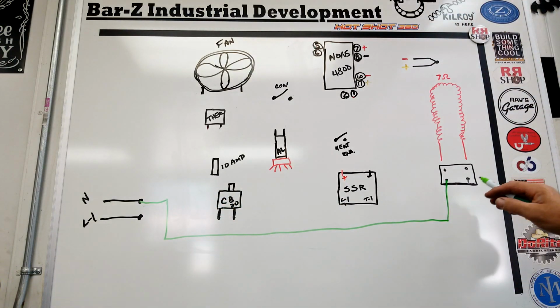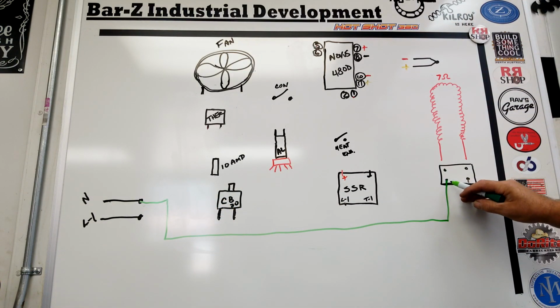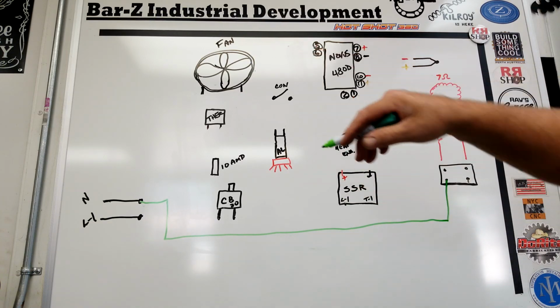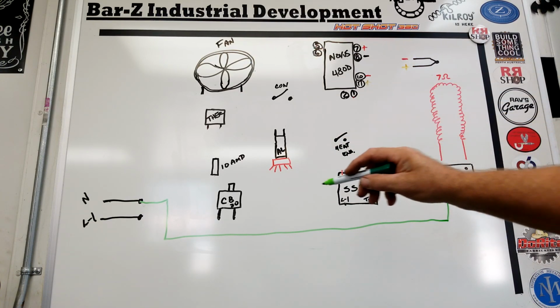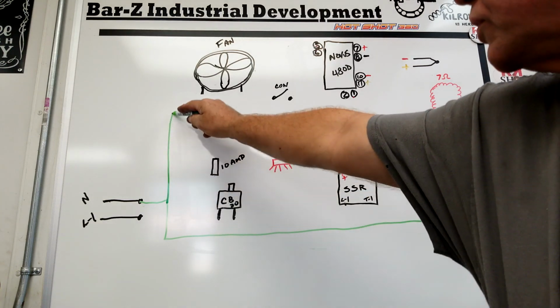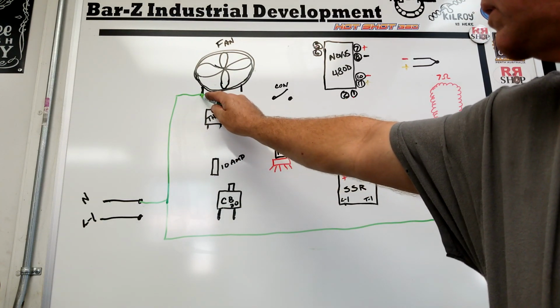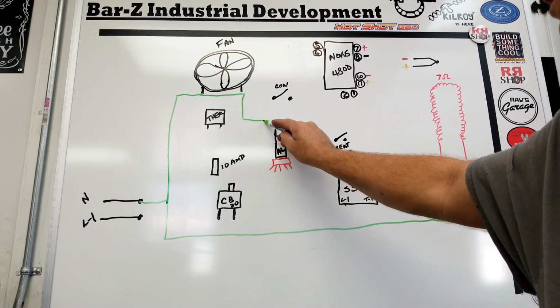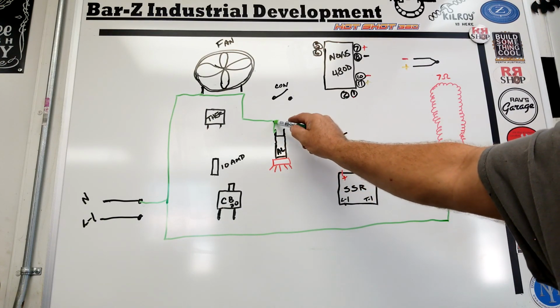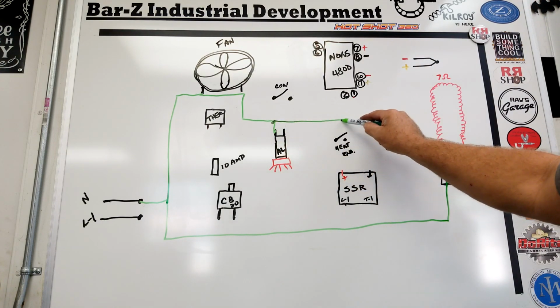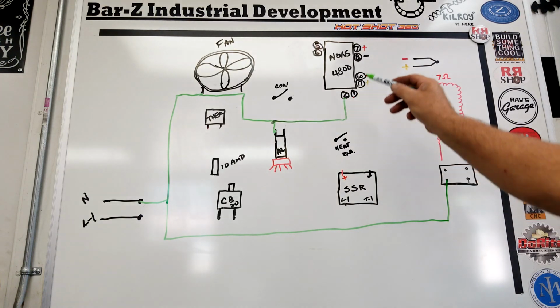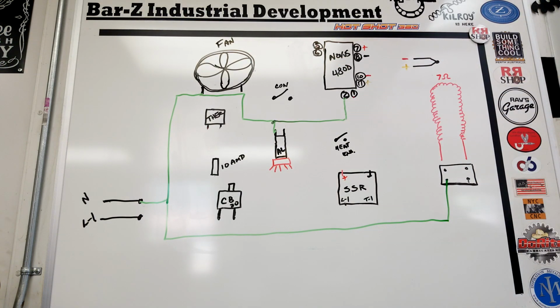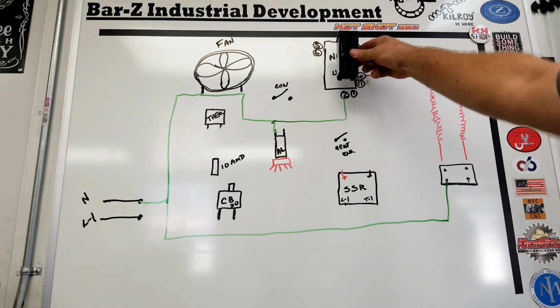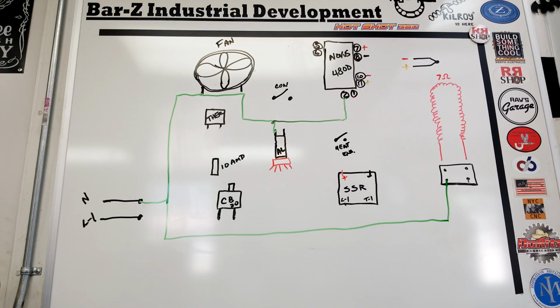All right. Out of there, we're going to distribute neutral and backfeed it out and take it back out to everything else that needs neutral, which includes your fan, your alarm, and your Novus temperature controller. So this right here represents that, the Novus. All right, so we've got neutral to everything that needs neutral.